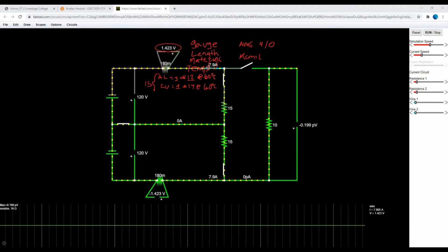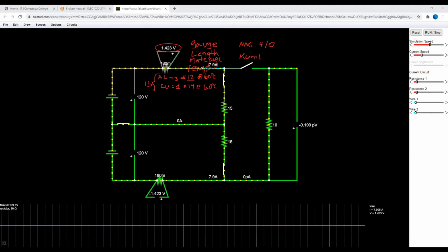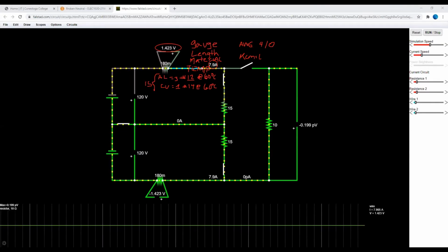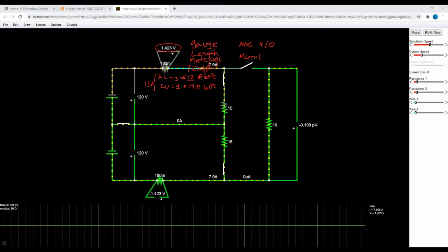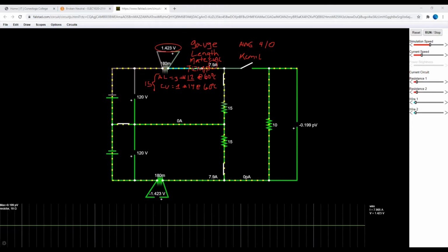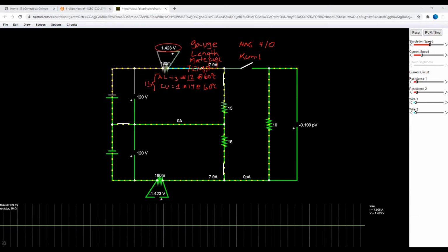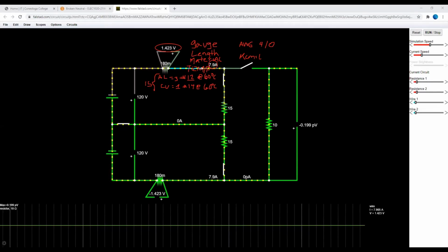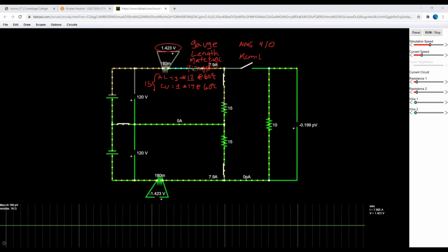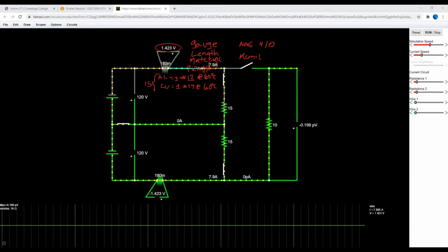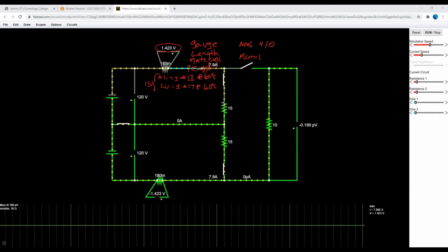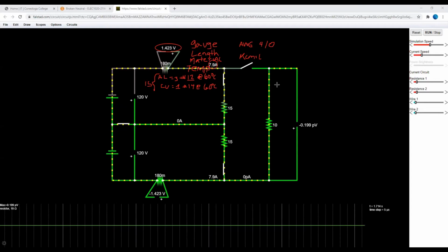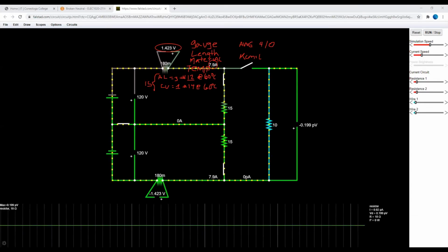Especially when you use table 5A, which is for temperature. Once you go beyond 30 Celsius, then you have to derate your conductors. In today's class, we are going to do all our calculations with a table which is rated at 30 Celsius, the standard table which is used in Delmar's. Any questions about this portion, or can we move on?